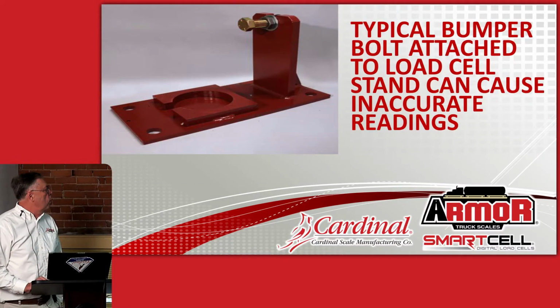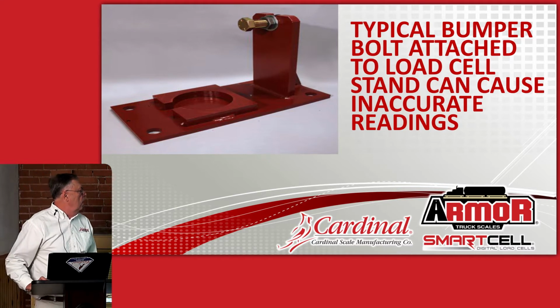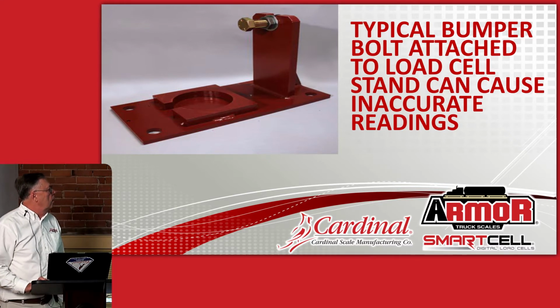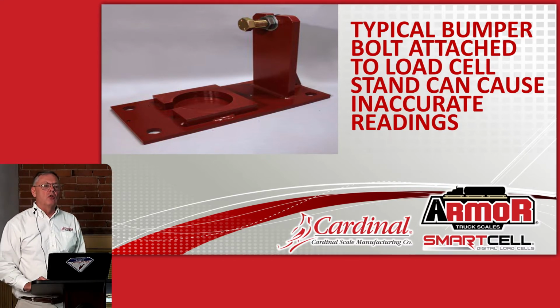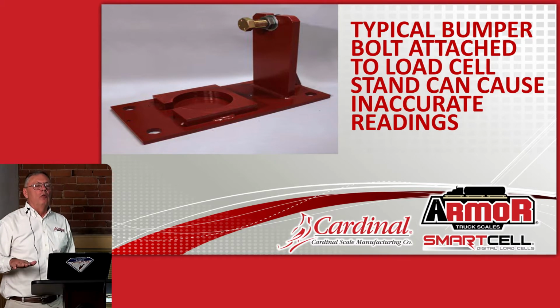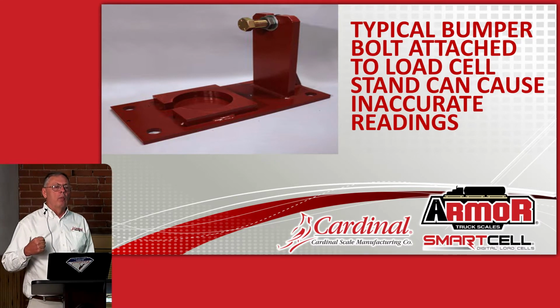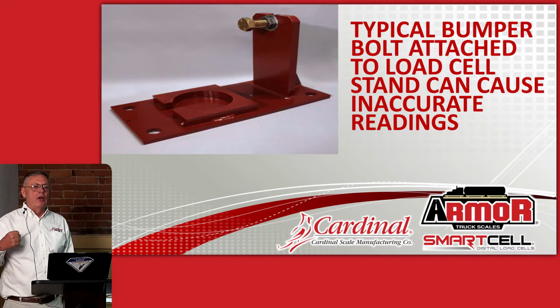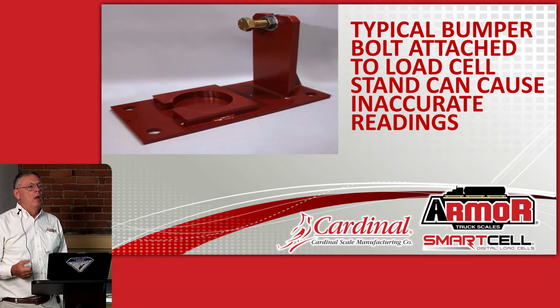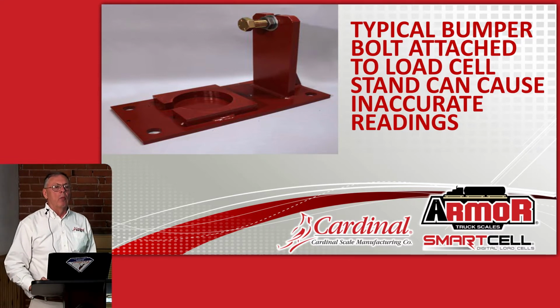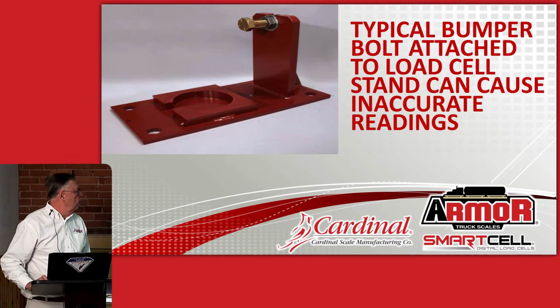This is about the worst example of a checking system that I could think of. There they have a bumper bolt that's attached to the actual base that the load cell sets on. So every time the weighbridge hits that bumper bolt, they're actually shocking the base of the load cell. And I wouldn't think that it'd stay in calibration very long like that.